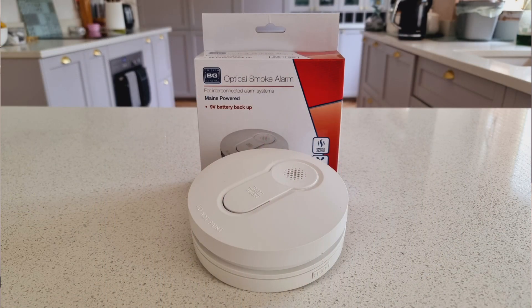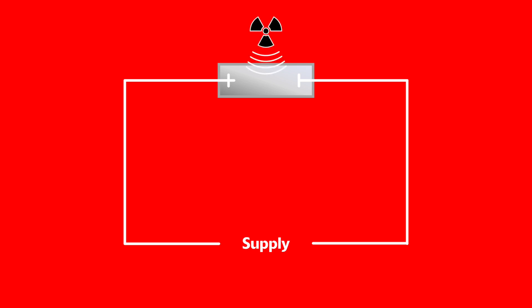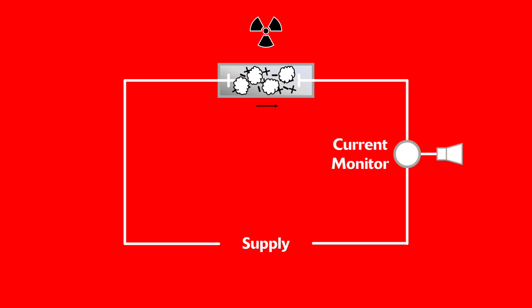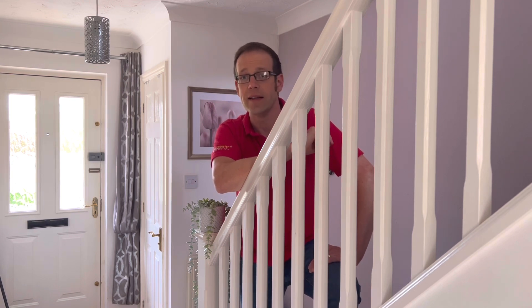Smoke detectors break down into two subcategories: ionisation and optical. An ionisation smoke has a small chamber with a circuit and an electrode at either end. Normally no current would flow, but the chamber is filled with radiation from a small amount of radioactive material, usually americium-241. This ionises the air in the chamber, allowing current to flow. If smoke enters, the ionisation is reduced, the current finds it harder to flow, and the alarm is triggered. This detector is more responsive to the small particles produced by a flaming fire, but less responsive to the larger particles from a low smouldering fire.